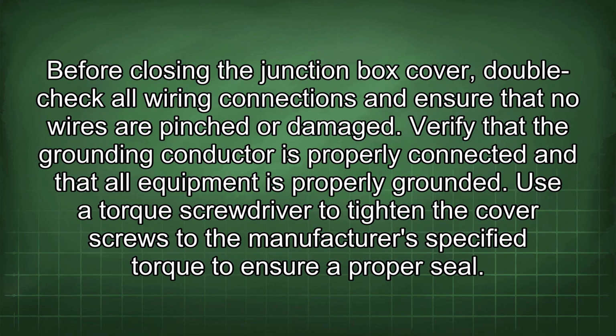Before closing the junction box cover, double-check all wiring connections and ensure that no wires are pinched or damaged. Verify that the grounding conductor is properly connected and that all equipment is properly grounded. Use a torque screwdriver to tighten the cover screws to the manufacturer's specified torque to ensure proper seal.